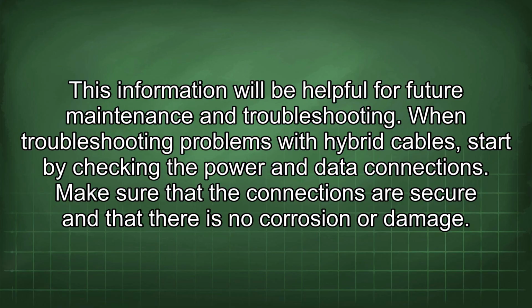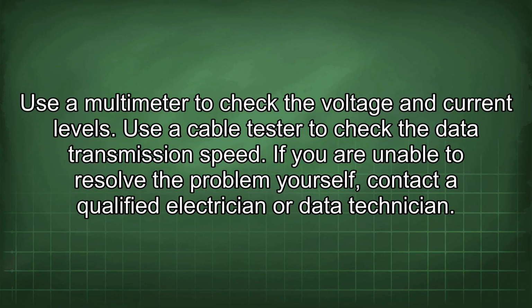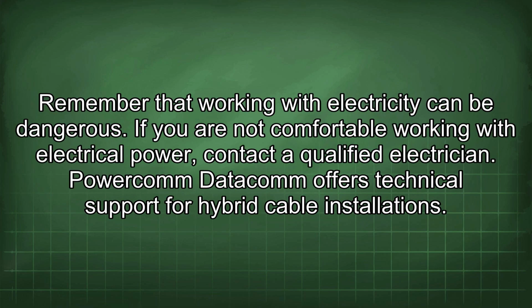When troubleshooting problems with hybrid cables, start by checking the power and data connections. Make sure that the connections are secure and that there is no corrosion or damage. Use a multimeter to check the voltage and current levels. Use a cable tester to check the data transmission speed. If you are unable to resolve the problem yourself, contact a qualified electrician or data technician. Remember that working with electricity can be dangerous. If you are not comfortable working with electrical power, contact a qualified electrician.